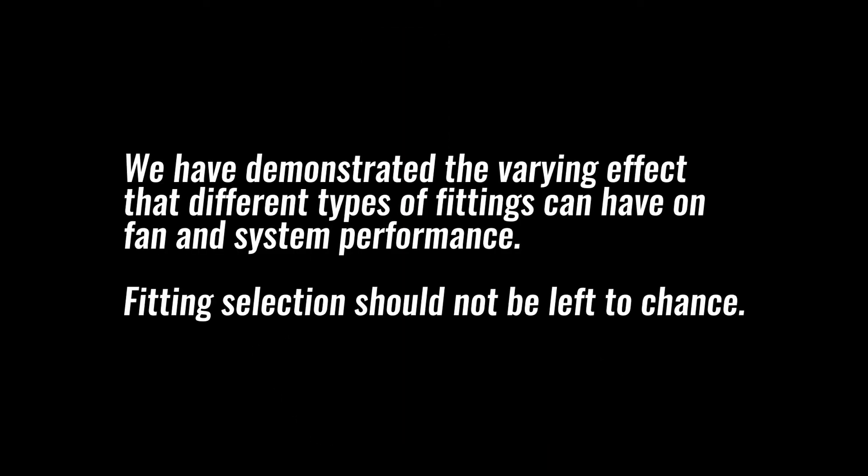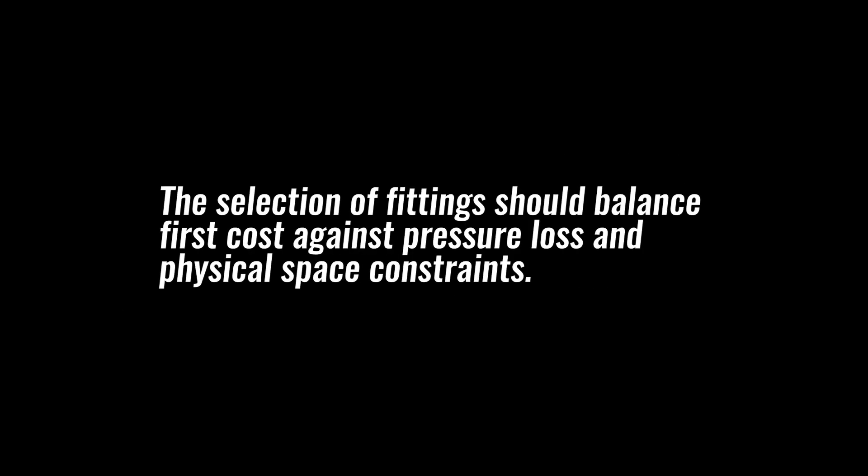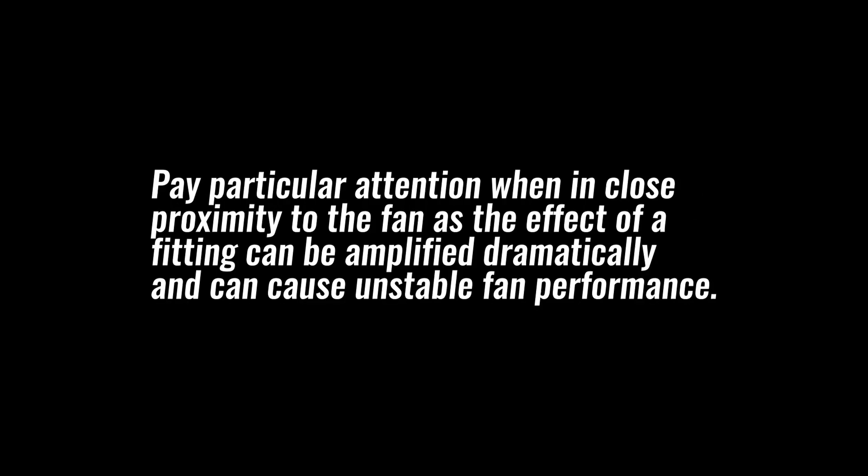Summarizing, we have demonstrated the varying effect that different types of fittings can have on fan and system performance. Fitting selection should not be left to chance. The selection of fittings should balance first cost against pressure loss and physical space constraints. Pay particular attention when in close proximity to the fan as the effect of a fitting can be amplified dramatically and can cause unstable fan performance.